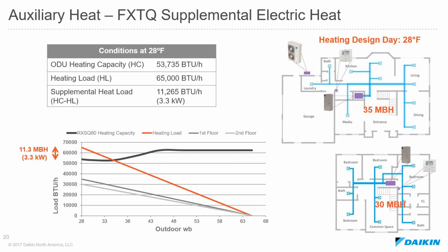Now looking at that same example, but the only thing I've changed here is the climate. So it's a more temperate climate, with a heating design temperature of 28 degrees. So maybe that's northern Texas, which could have a design day temperature of 28 degrees. So total load is 65. This is an all heat pump solution. In this scenario, based off 28 degrees, our outdoor unit heating capacity is going to be 53 MBH, and our heating load is 65. So we're a little bit short.